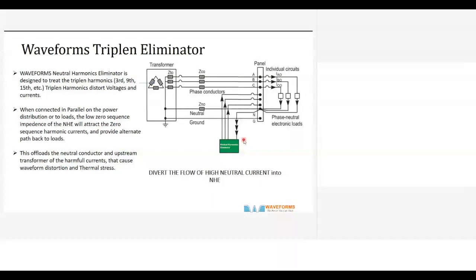Connection is also a very simple exercise. Connected in parallel on the power distribution or load, the low zero sequence impedance of the neutral harmonic eliminator will attract the zero sequence harmonic current and provide an alternate path back to the loads. So the neutral is offloaded. This offloads the neutral conductor and upstream transformer of the harmful current that causes waveform distortion and thermal stress.